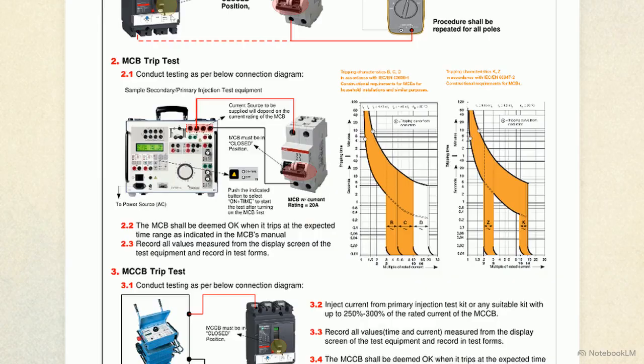This chart displays logarithmic time current curves. The validation requirement is measuring the exact millisecond the breaker trips and plotting that time against the injected current. The coordinates must fall within the shaded orange tolerance band, otherwise the breaker is defective. Verifying that precise fraction of a second ensures the MCB physically opens the circuit fast enough to stop an overcurrent from damaging the upstream wiring.